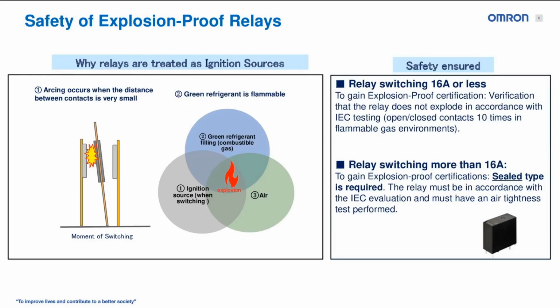What does that have to do with relays? That has to do with the ignition source that relays add to the equation. Being an ignition source, because they have some arcing that can occur between the contacts when they're breaking or making in operation. There can be some arcing where the electric current will jump from one contact to another contact, which can ignite the combination of a green refrigerant, which is semi-flammable, and the air and cause an explosion. So we need there to be a safe option for this transition to these types of refrigerants.